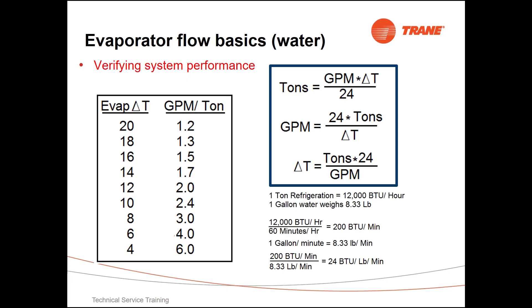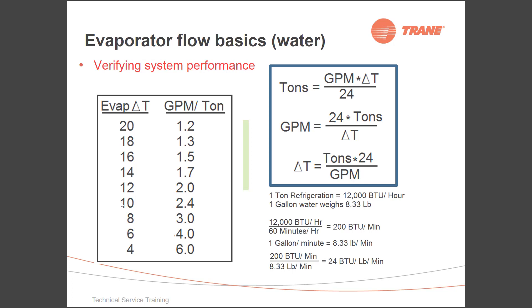So if I had a 100 ton chiller, that would mean that I would be pumping 240 gallons per minute through the chiller, and a 10 degree delta T would confirm that.